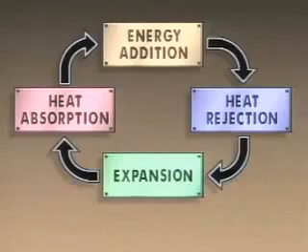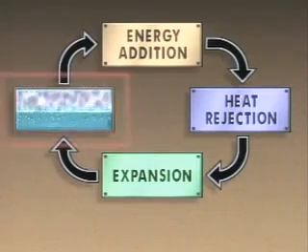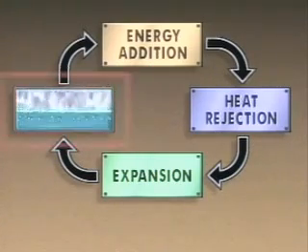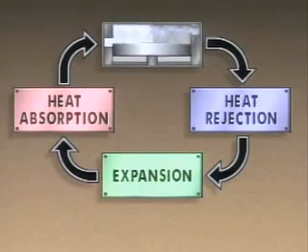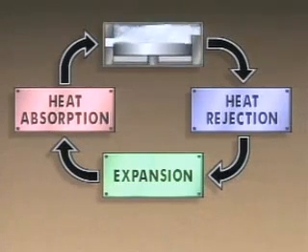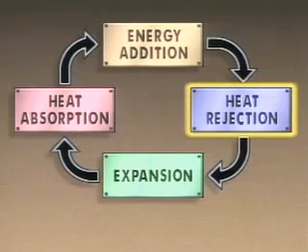The heat absorption step causes the refrigerant to change phase from a liquid to a vapor. The vapor also receives heat and its temperature increases, so the refrigerant changes from a low temperature liquid to a higher temperature vapor. In the energy addition step, energy is added to the refrigerant so it can move through the rest of the refrigeration cycle. In this step, also called the compression step, the refrigerant vapor from the absorption step is compressed, which increases the refrigerant's pressure and temperature.